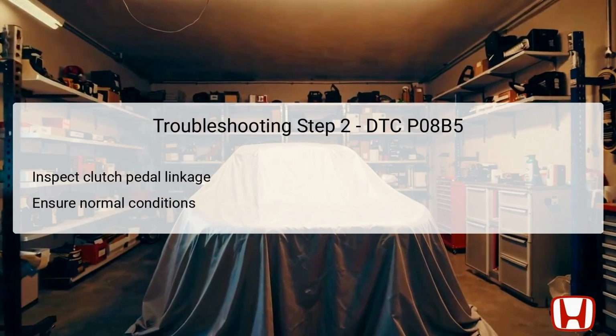In the second troubleshooting step, the focus shifts to the clutch pedal linkage connected to the clutch pedal stroke sensor. Inspecting the linkage is essential because a loose or damaged connection could lead to erroneous signal readings. The technician needs to ensure that the pin linking the clutch pedal to the sensor is secure and intact. Normal conditions dictate that the pin must not come off.